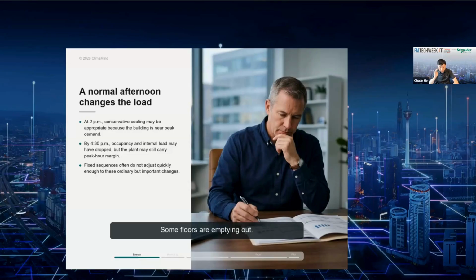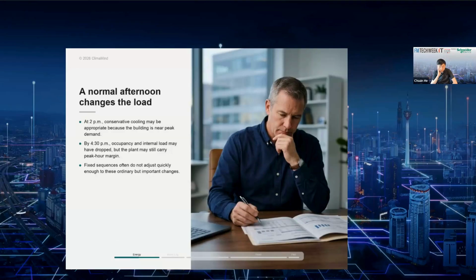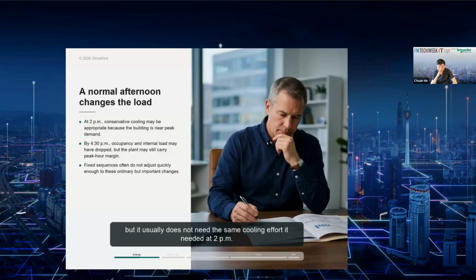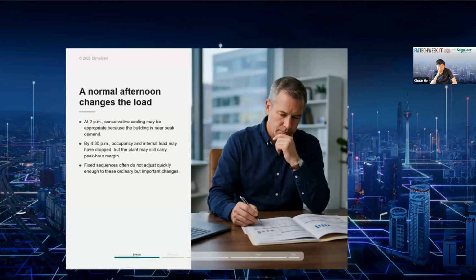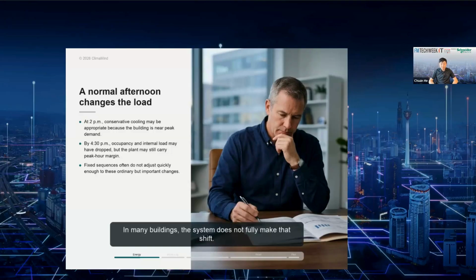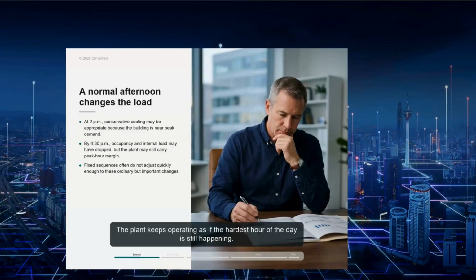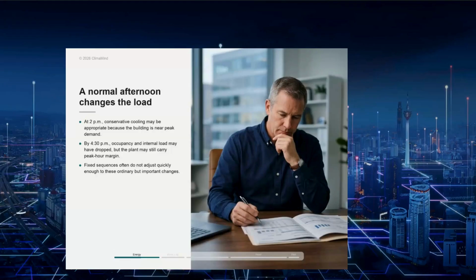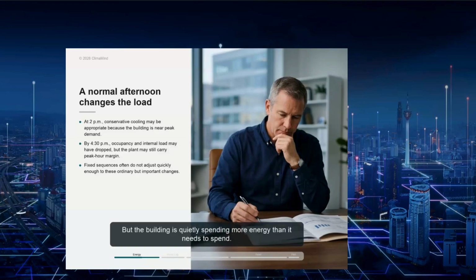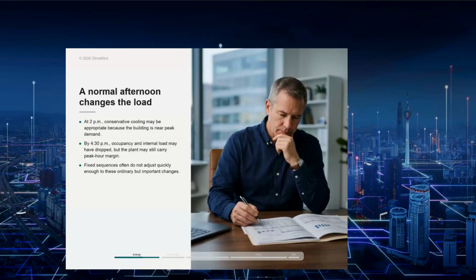Some floors are emptying out. Internal heat has started to fall. The sun angle is different. The building still needs cooling, but it usually does not need the same cooling effort it needed at 2 p.m. In many buildings, the system does not fully make that shift. The plant keeps operating as if the hardest hour of the day is still happening. Nothing looks broken, comfort is still fine, but the building is quietly spending more energy than it needs to spend. That is the problem hiding in plain sight.